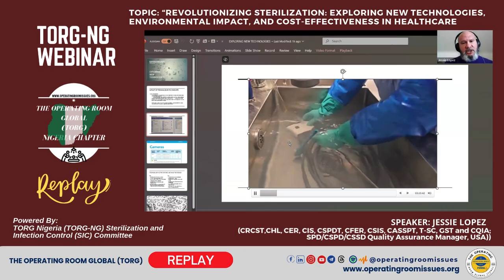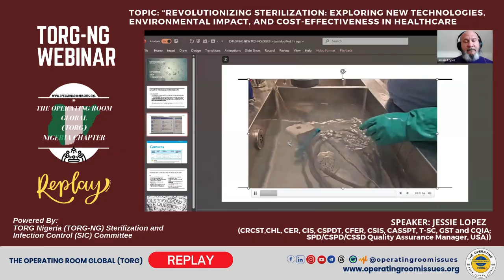This device has 2 lumens in it. And in those lumens, we cannot add pre-treatment into those lumens because it may be difficult to rinse out or remove. And with that being said, the soils in there will dry and make it very difficult to remove. So what you seen me do just now was called priming the channels. And that's filling my channels with detergent to allow the detergent to work its magic inside of the lumen.